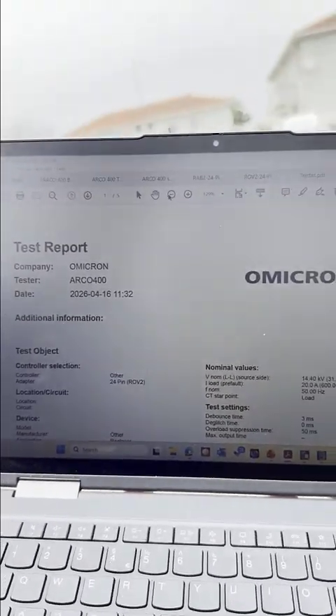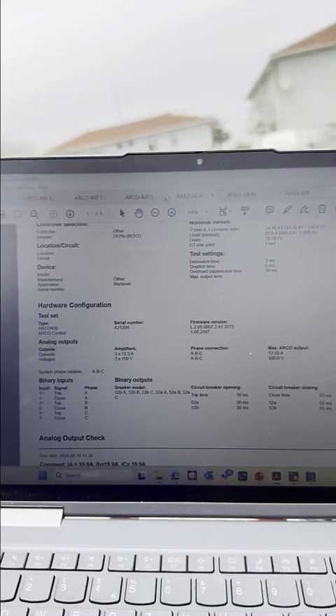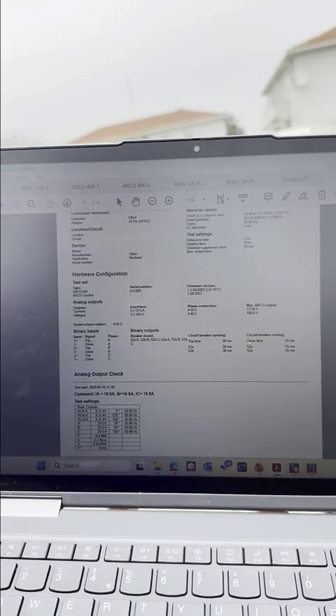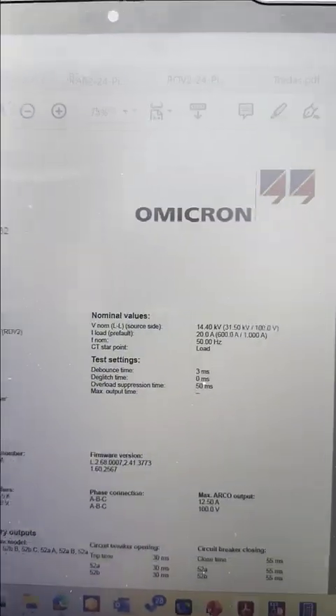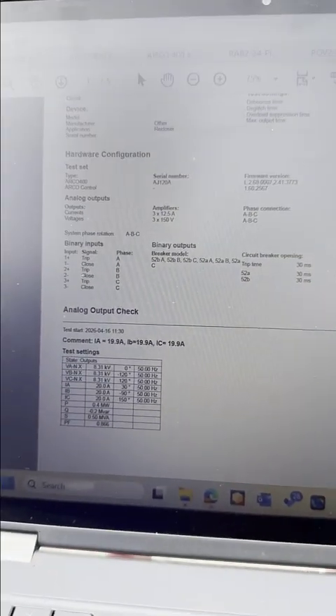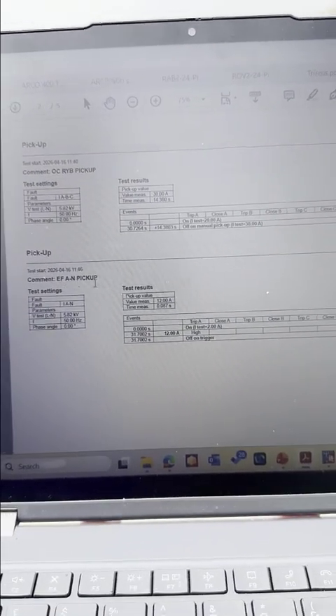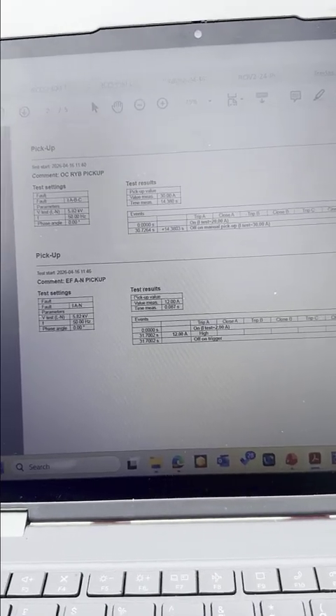You can see from here all the tests, the time and the date stamp. Also the CT ratios, the VT ratios, and the adapter used in our test scenarios. And here is a comment I have added, for the IA, IB, IC wiring check, then the backup test for the overcurrent RYB test, and here is the value measured at 30 amp. Also the backup for the earth fault A to N at 12 amp.